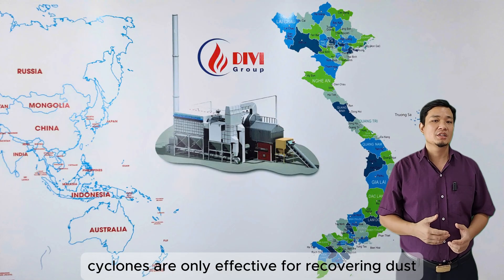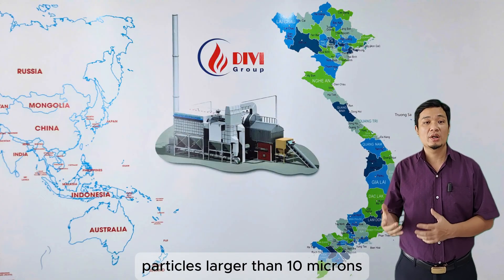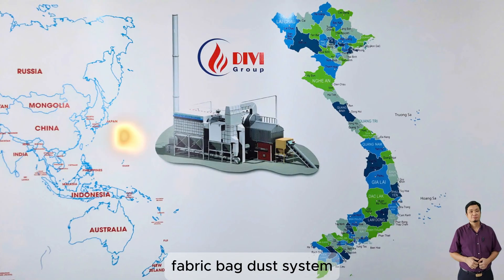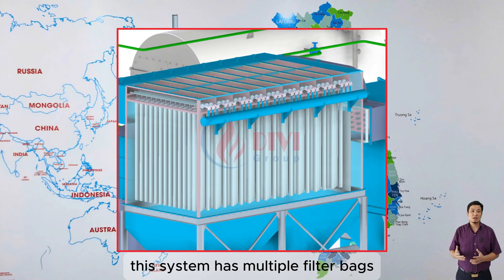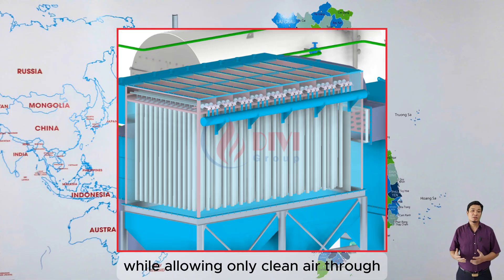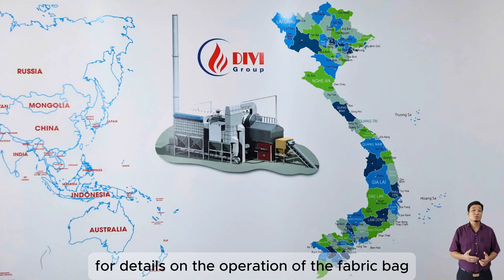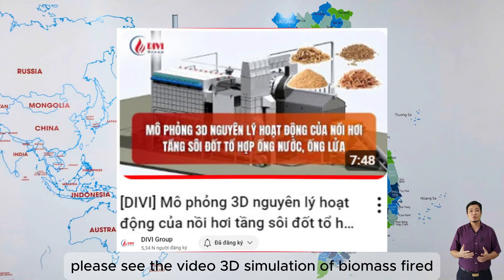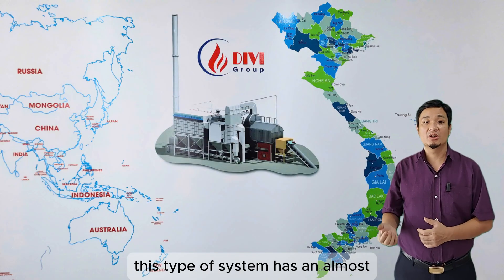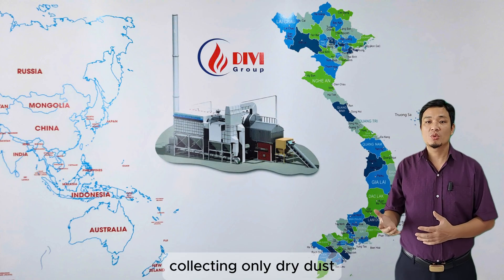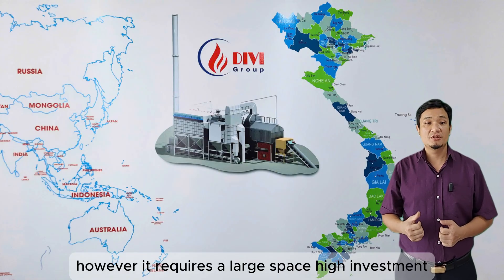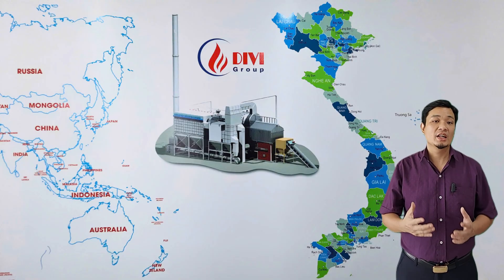For finer particles, other types of dust recovery systems are required. Fabric bag dust system: this system has multiple filter bags through which the smoke passes, trapping dust particles while allowing only clean air through. This type of system has an almost absolute dust recovery rate, collecting only dry dust, and the emissions appear nearly colorless. However, it requires a large space and has high investment and maintenance costs.